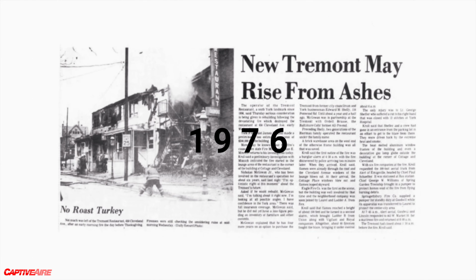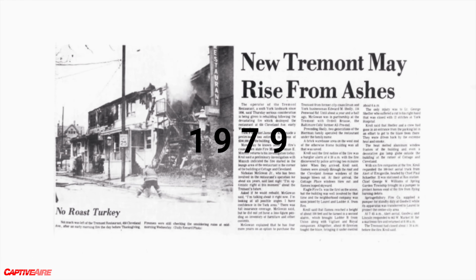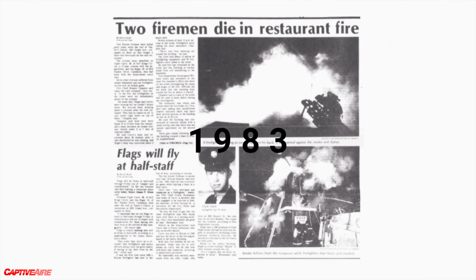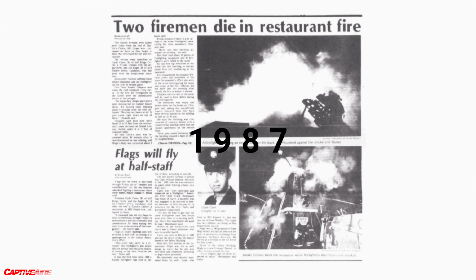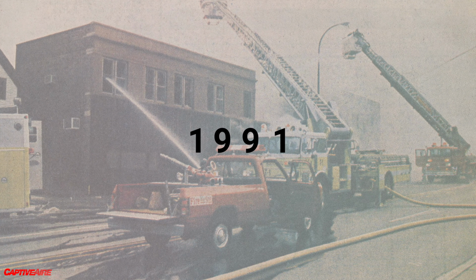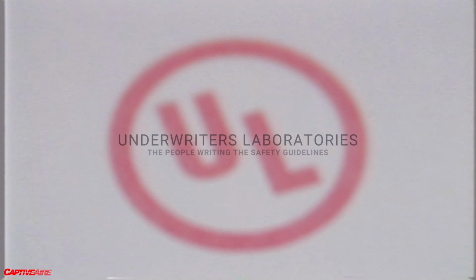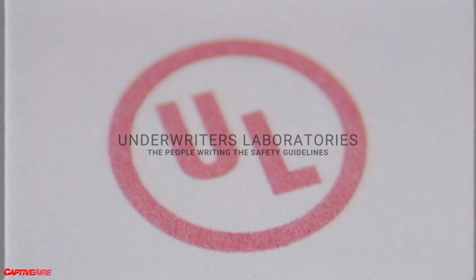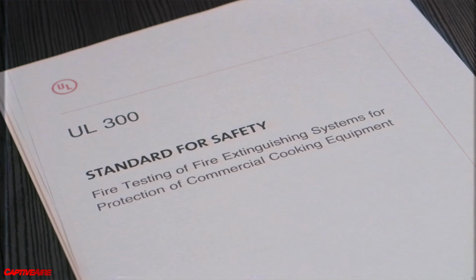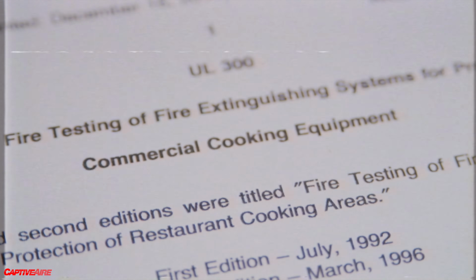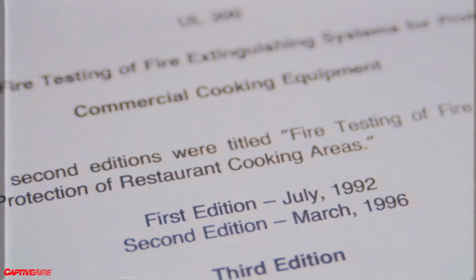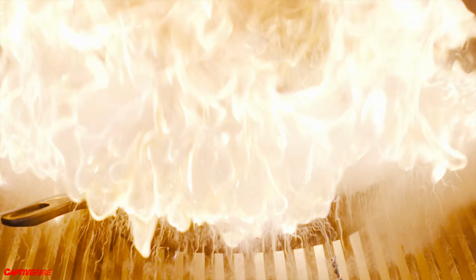It took a long time for a change to be enforced in the industry, and in the meantime, deep fryer fires destroyed many kitchens and even entire restaurants across the country, until 1994. It's actually a pretty important date in the fire suppression world. UL realized that the industry was cooking with more vegetable oils at higher temperatures, so we needed a change. And that change was we switched from a dry chemical system to a wet chemical system to suppress fires.